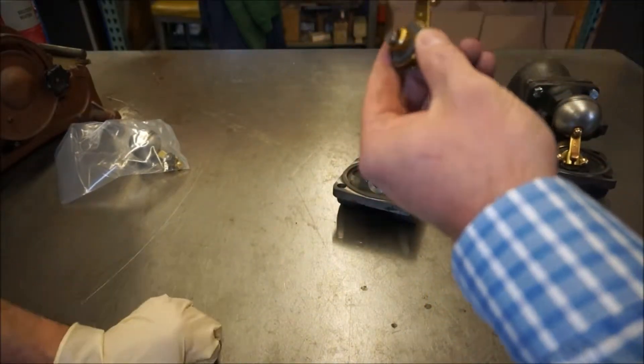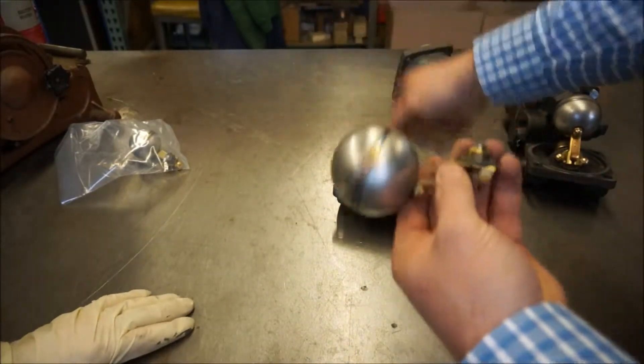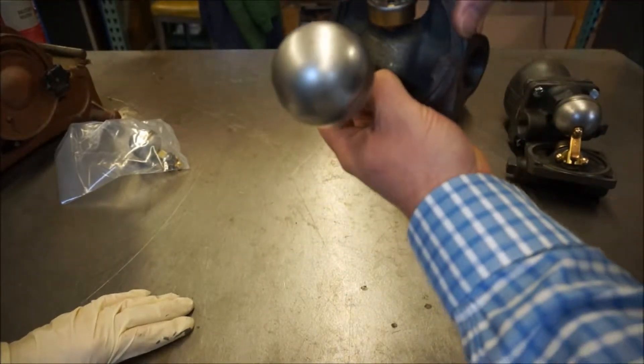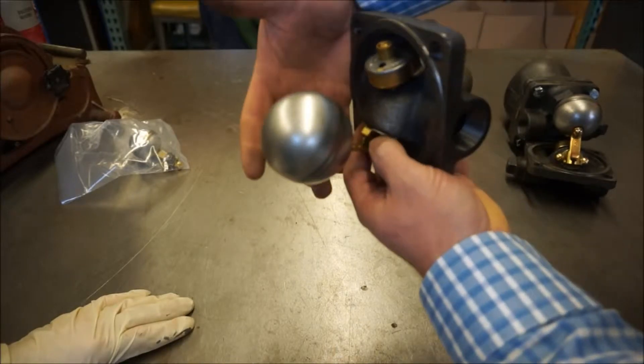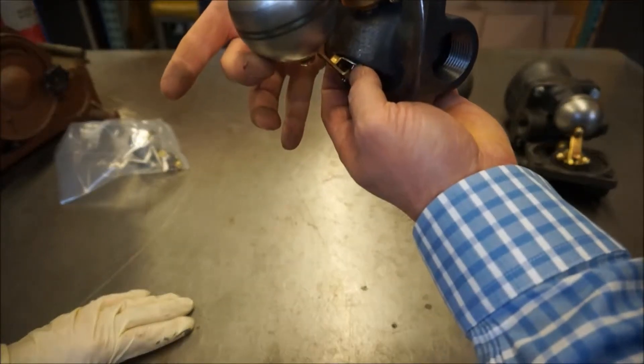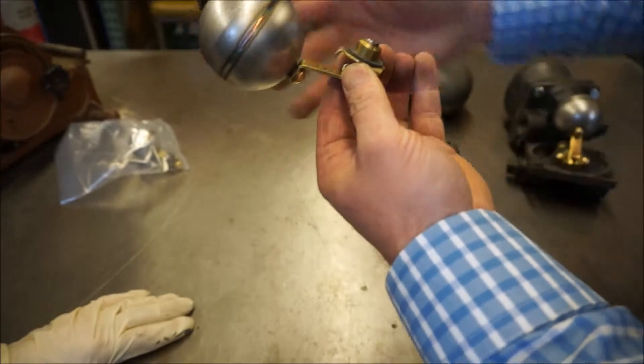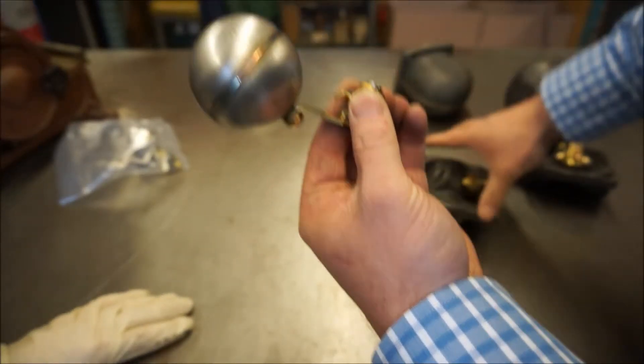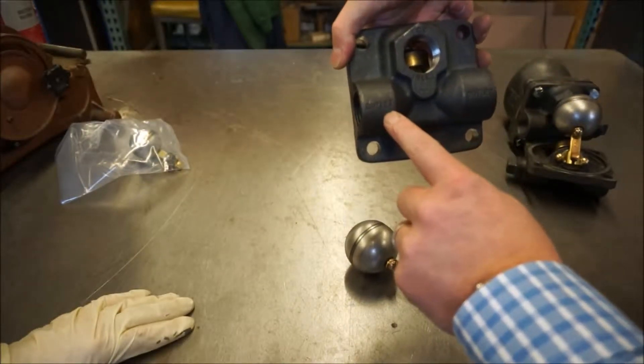The float with the seat and the plug screw in here. And when the trap fills up with condensate, it floats the float, which then opens the seat and allows the condensate to flow out the outlet.